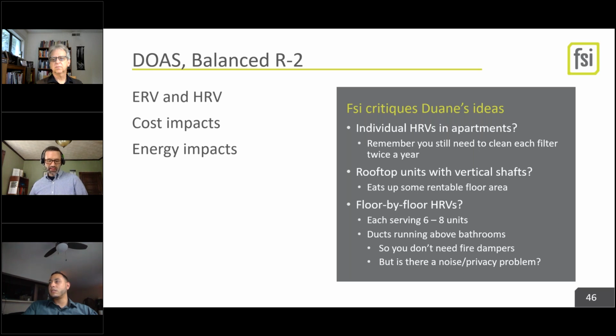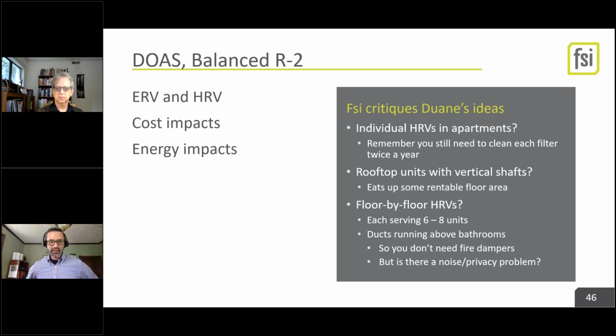So this is straight out of ASHRAE 62.1. So let's define that term first. In an energy recovery wheel, like that orange circle I showed you, that wheel is spinning. So you get that teeny little bit of air that carries over into that other side. And so ASHRAE 62.1 defines classes of air, and depending on what class of air you are allowed to have 10% or 5% bypass.